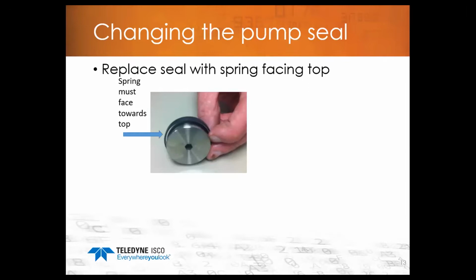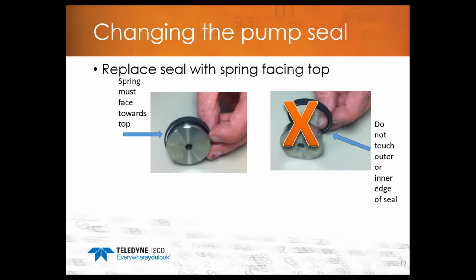When you replace the piston seal, after you've removed the old one from the piston retainer, when you put the new one on, you always want to make sure that the spring side of the seal is facing upwards. We have had occasions where the seal gets put on upside down and it leaks when they try to run it. So always make sure that when you replace the seal, that spring side is facing upwards. You don't want to have the spring side facing down, and you try to not handle the seal a whole lot. Be careful when you're replacing it, because it is easy to nick the seal if you're not careful.